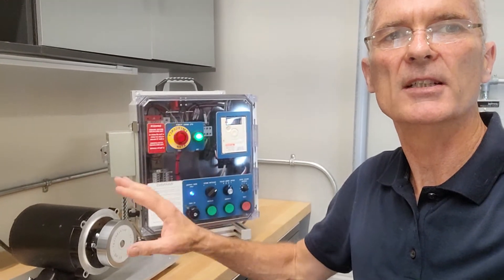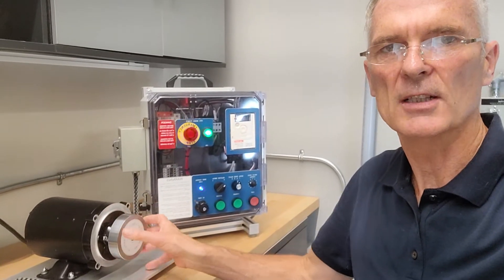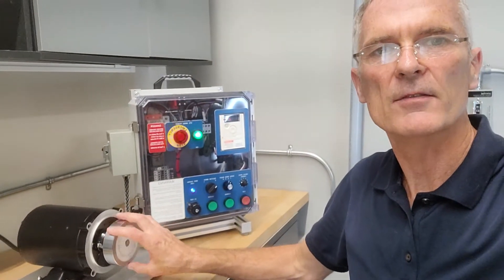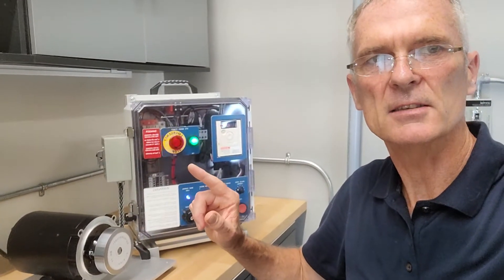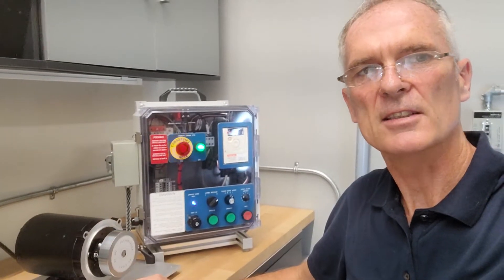In the case of this drive, it's a little bit different. What it will do is set up DC injection automatically at a standstill, and what it'll do is prevent freewheeling of the rotor. They're not all set up the same way - you need to read the manual on the drive that you're working with. Let's have a look at this one.